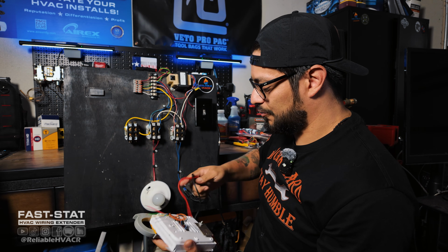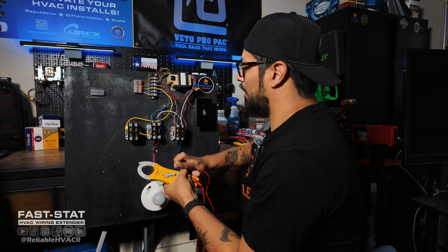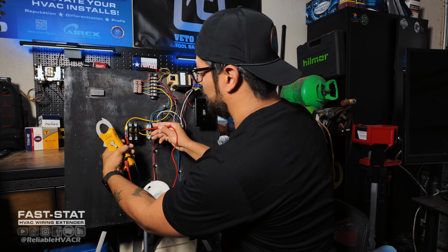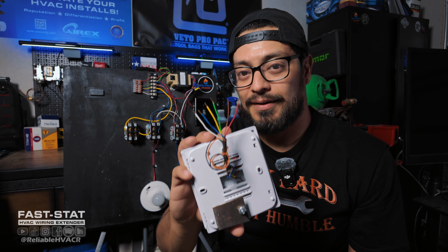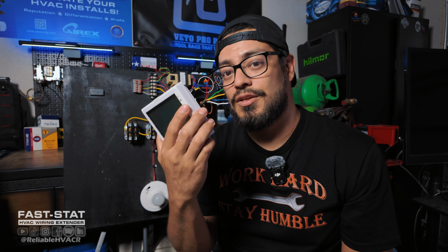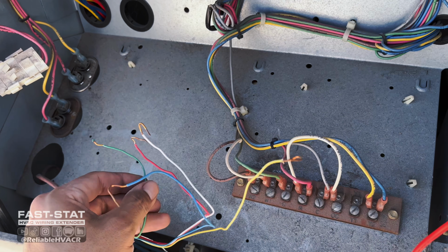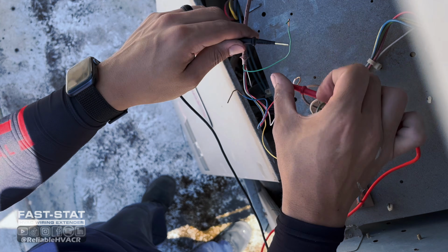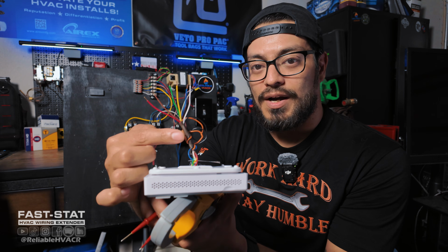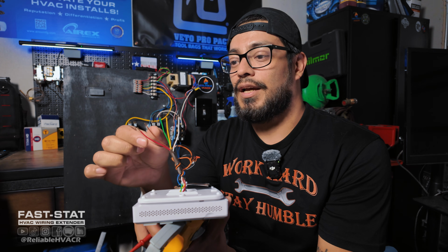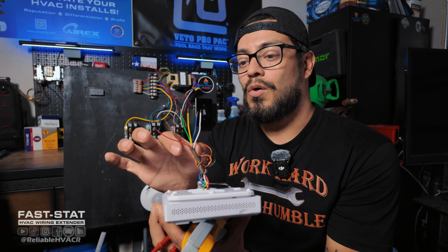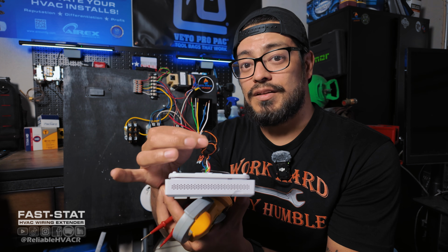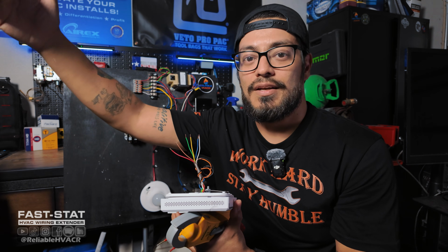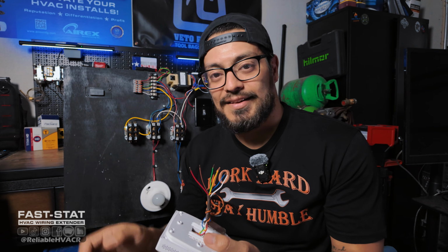Now, when they're connected, you might get a tone if any of the wires land on the contactors, because that's a coil. You're going to get continuity on that. So when you do check continuity, I know people prefer resistance, prefer this or that. Make sure you unplug any wire. So if you want to isolate this thermostat, you isolate it here and you isolate it off the board. You remove all those wires from the control board or the control, and then you start checking continuity to ground. This thermostat wire itself is what I'm concerned about, that it's grounded. And that could be, like I said, either this rubbed out on metal or this deteriorated and you have an issue internally on the wire between the unit and through the building back out. When you isolate your wires, that's what you want to check.